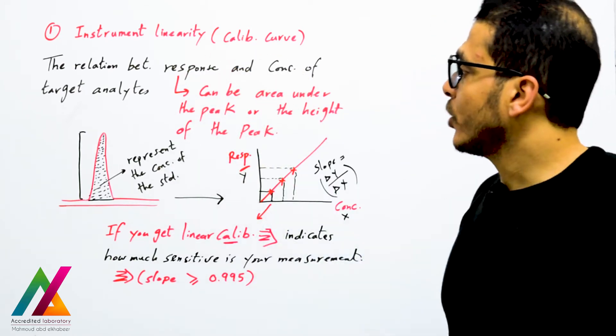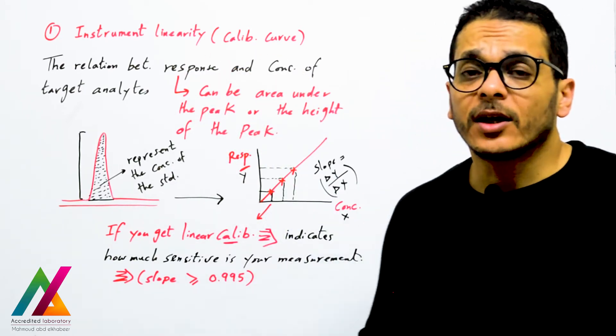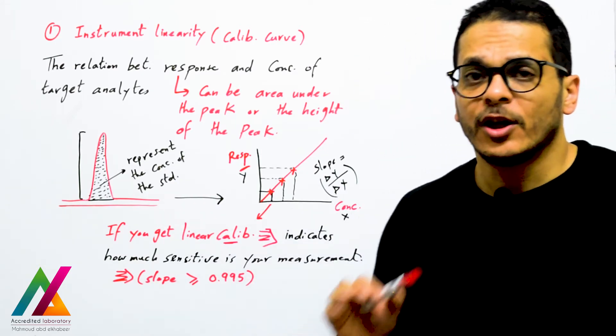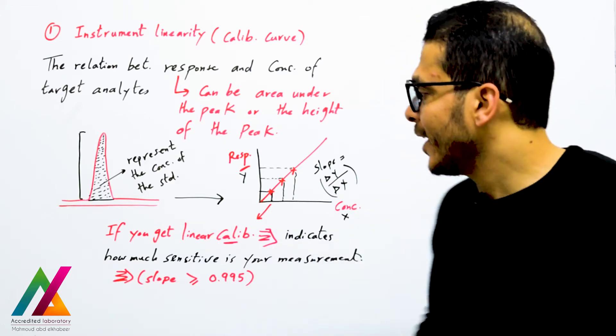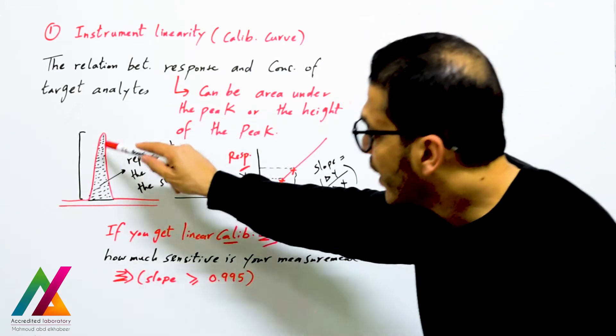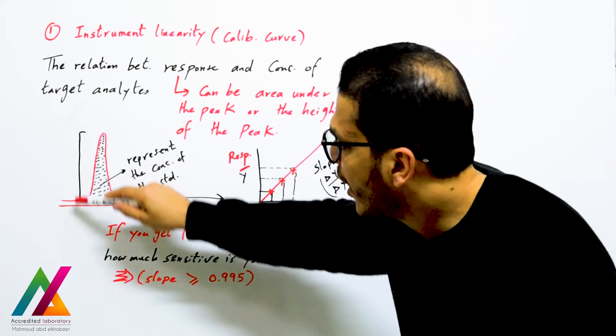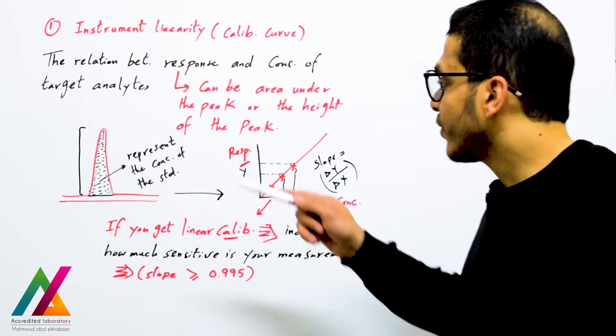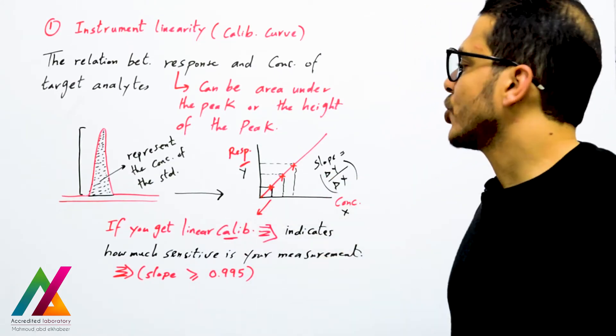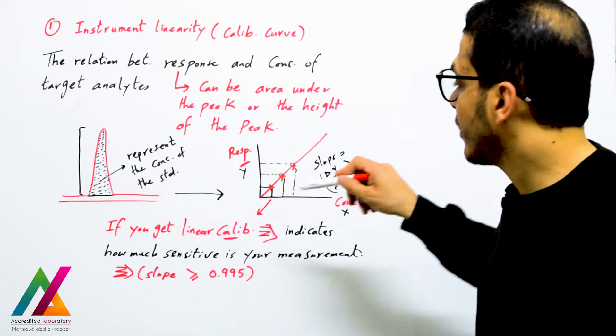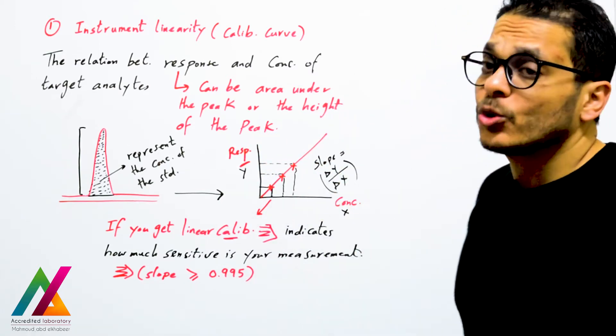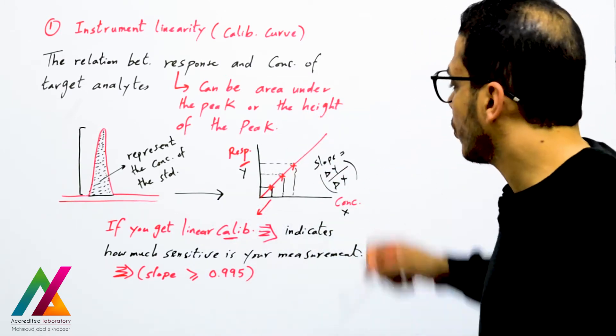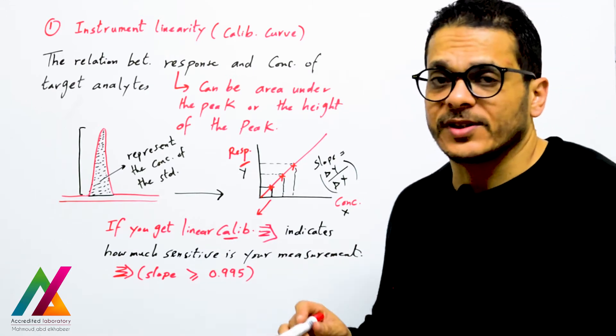Instrument linearity, or the calibration curve, is the relation between response and the concentration of target analytes. The response in chromatography can be the area under the peak or the height of the peak. When you run any calibration standard for your target analyte, you get a peak, and each calibration standard gives one point on this line — the relation between response on Y and concentration on X.